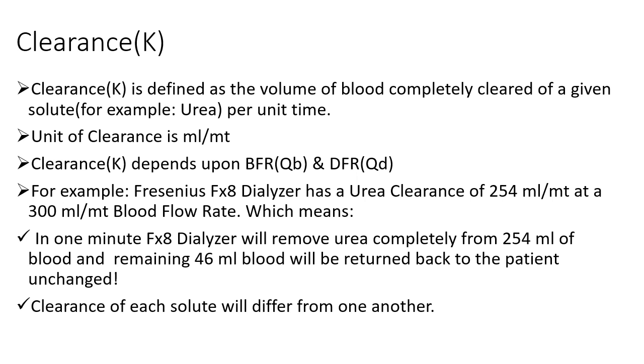The unit of clearance is milliliters per minute, and clearance always changes with blood and dialysate flow rate. If you change the blood or dialysate flow rate, your clearance will also change. If you increase blood flow rate, clearance increases; if you decrease it, clearance decreases. The same applies to dialysate flow rate.